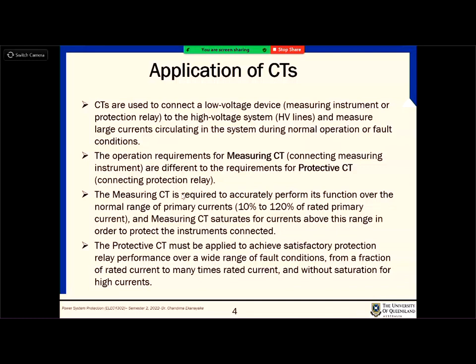You don't need to measure the fault current magnitude. What you need to know is that fault current is very high, right? So their accuracy is important in this range, 10% to 120% of the rated primary currents. So that is basically real loading conditions. Under real loading conditions, you need to know exactly how much current is going through.